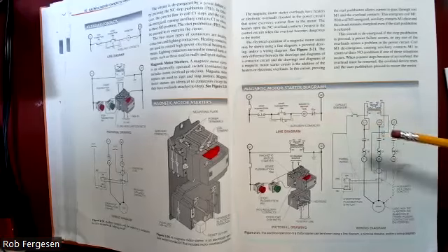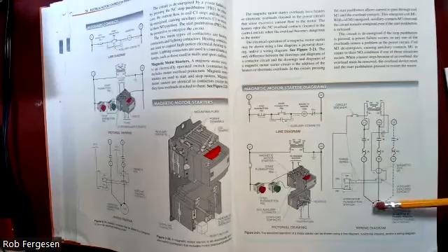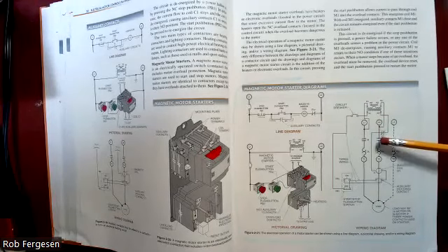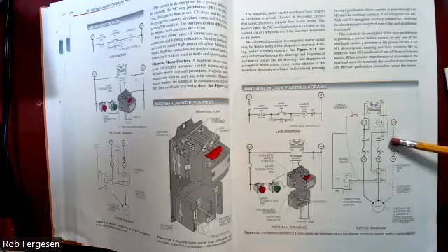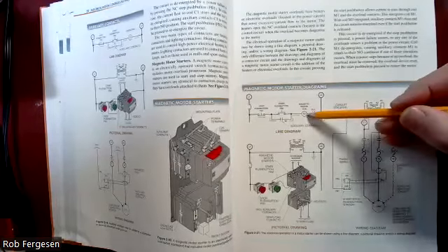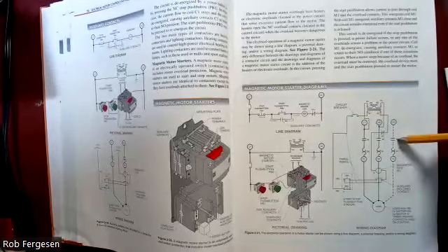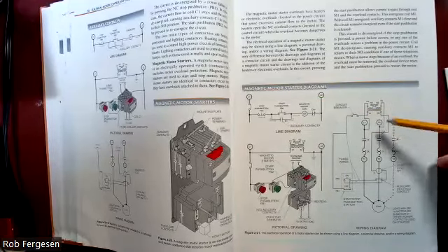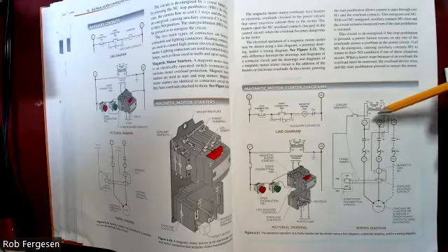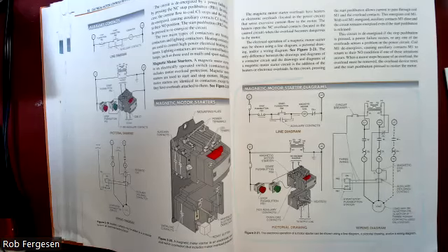And then over here, they show you the heavy duty wiring diagram where these contacts are closed by that little coil there. We know that they're connected because they're labeled that way. We use M1 and we see these contacts are labeled M. So that when I energize that coil, it closes these contacts, and then we can run current down through these wires to the load. In this case, the load is a big three-phase motor.